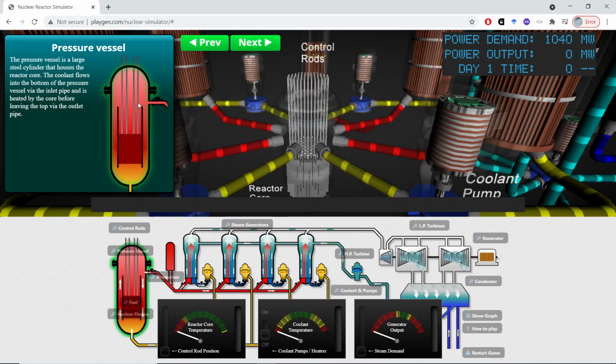So if it was the contrary, if the water entered from the top and went to the bottom and it started boiling, the boiling would reduce the velocity of the water around the boiling point, making it more likely for other parts of the reactor to start boiling.